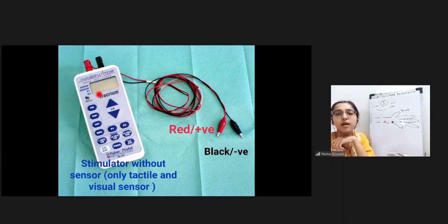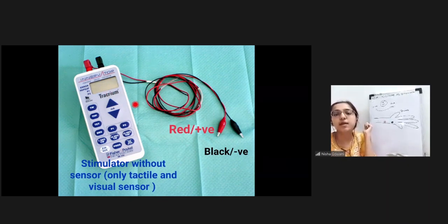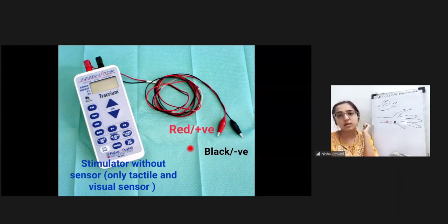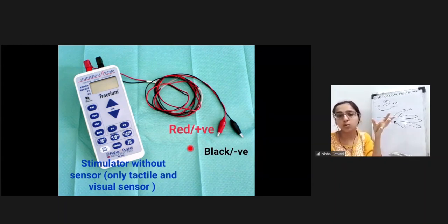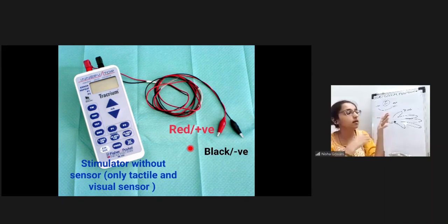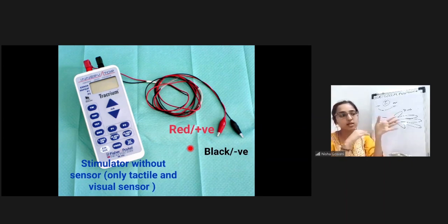There is a display where current and frequency can be seen. This stimulator has only the stimulating part - no sensor cable is visible. When there is no sensor, you see the muscle response visually and feel it tactilely. The anesthetist will feel the twitches in the patient's hand - that is tactile and visual sensing.